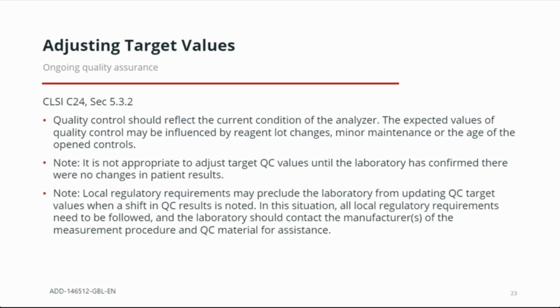Let's talk a little bit more about when we can make an adjustment and the value that doing so provides. This boils down to the reason we run QC material. QC material is designed to closely resemble patient samples. It's comprised of stabilized cellular components, and that matrix is designed to be sensitive to and influenced by conditions that affect patient samples. And we want it to alert the user to such changes before it impacts patient results.